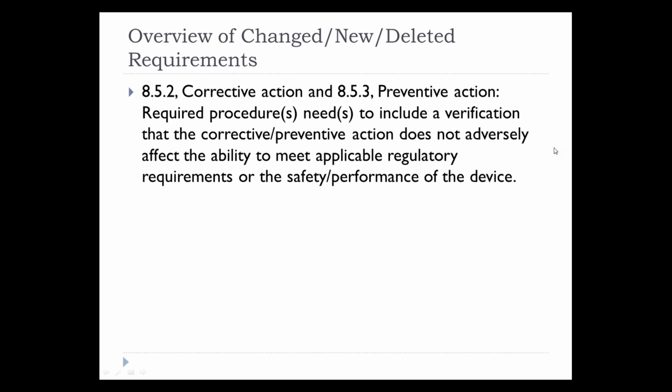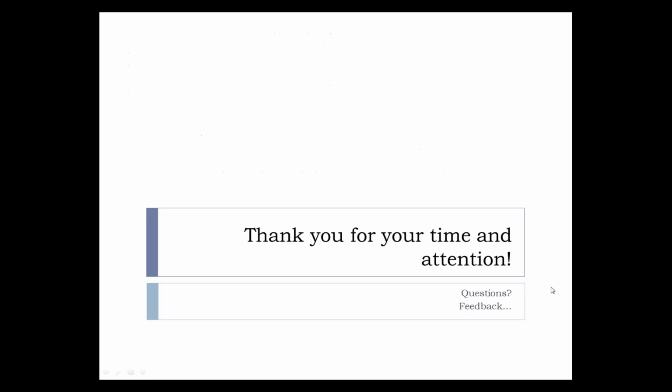Requirements in 8.5.2 under corrective action and 8.5.3 relating to preventive action need to include a verification that the corrective and preventive action that's chosen to be implemented does not adversely affect the ability to meet applicable regulatory requirements or the safety or performance of the device. So all that needs to be considered when determining appropriate corrective or preventive actions.